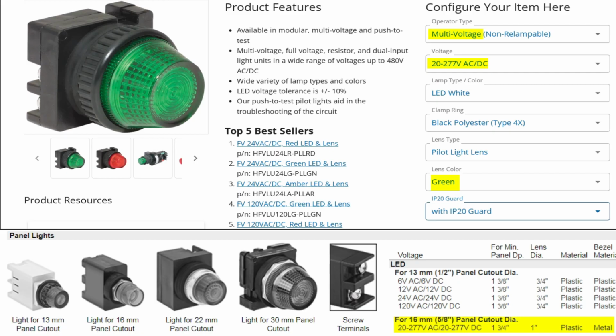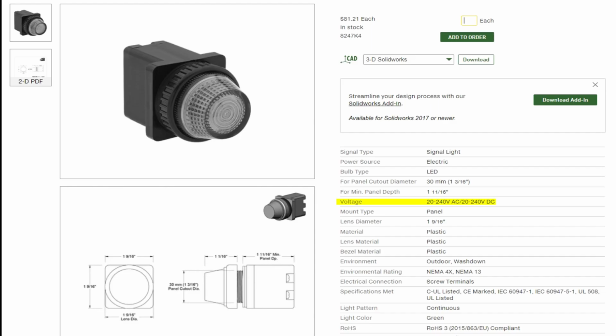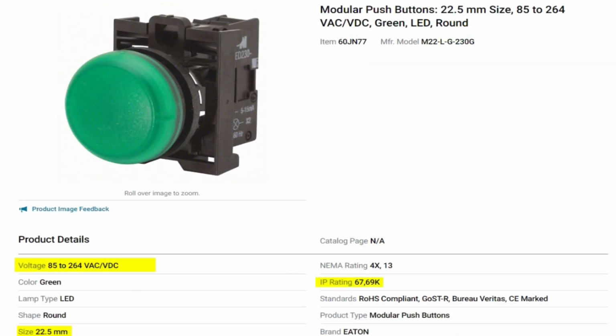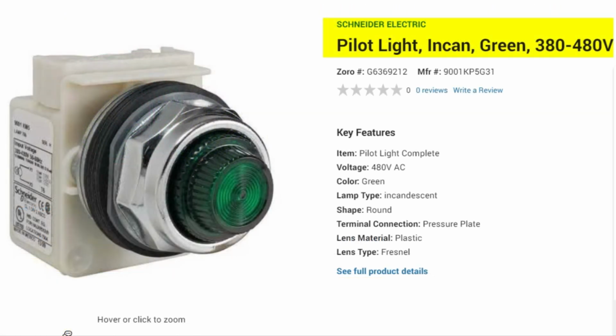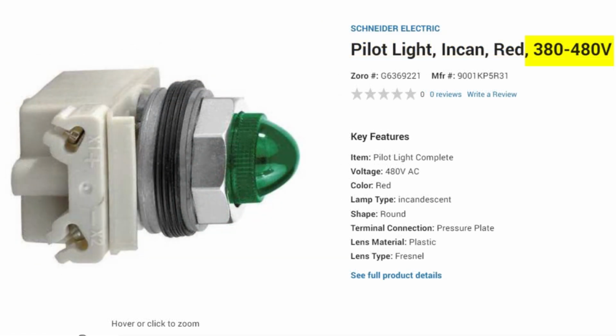Generally speaking, if you're planning on traveling within North America, you'll want to specify shore power indicator lights where the LEDs will accept a voltage range of 97 to 277 volts. If you're traveling in areas where 380 or 440 volts is used, you'll either need an LED which accepts a higher voltage range, or disconnect these indicators before plugging into shore power.